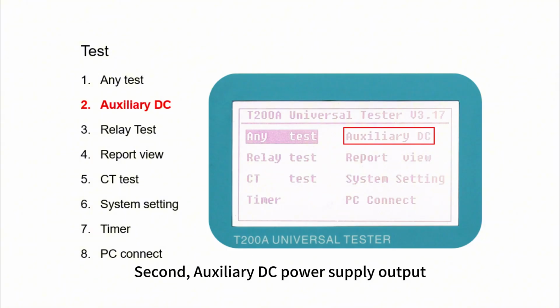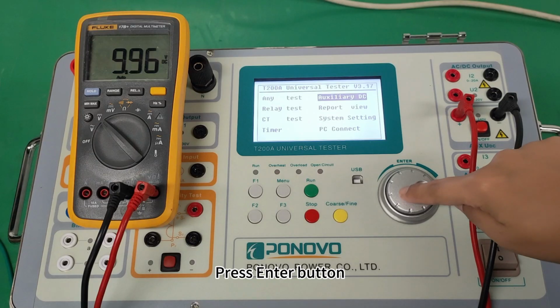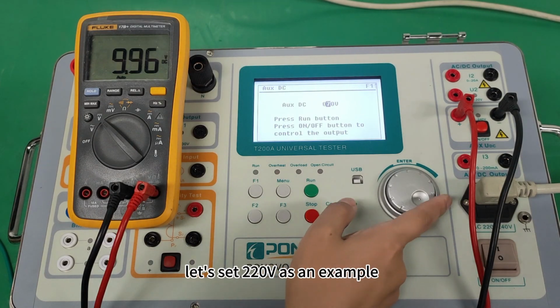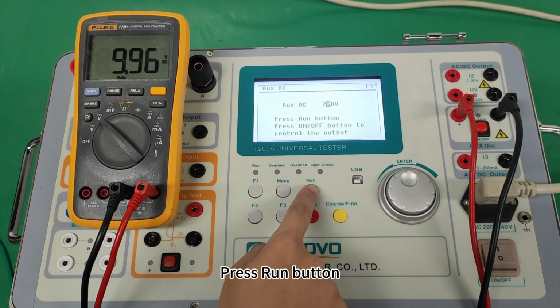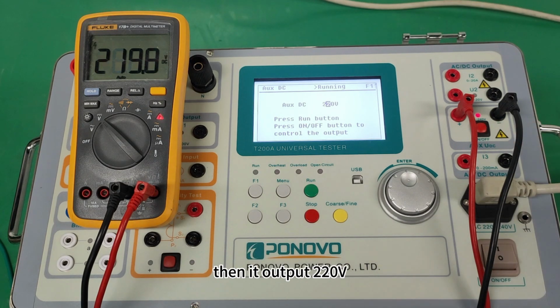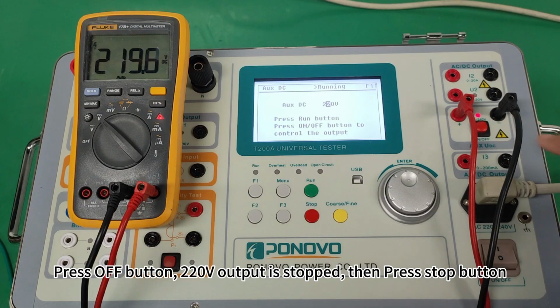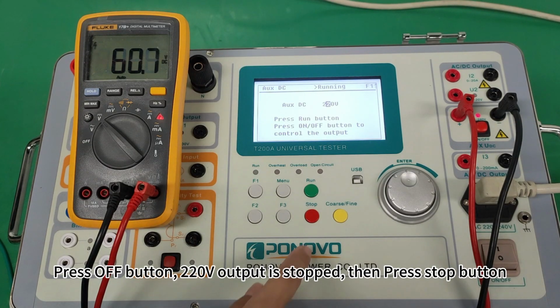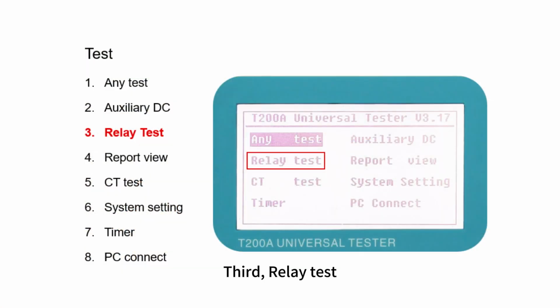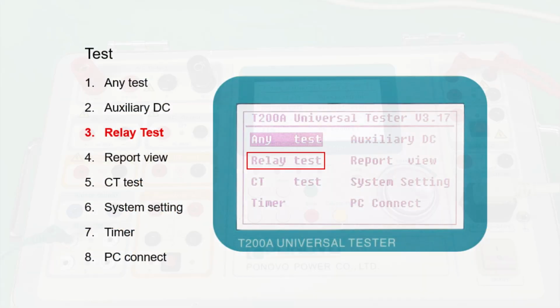Second, auxiliary DC power supply output. Press Enter button. Let's set 220 volts as an example. Press Run button, press On button, then it outputs DC 220 volts. Press Off button, 220 volts output is stopped. Then press Stop button. Third, relay test.